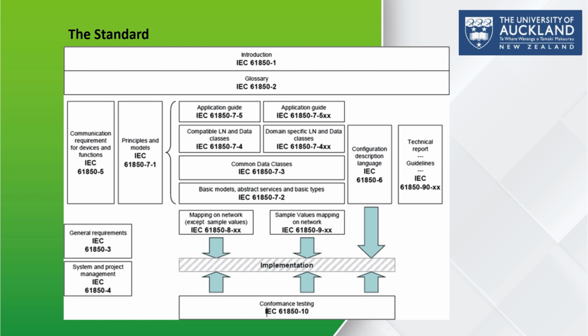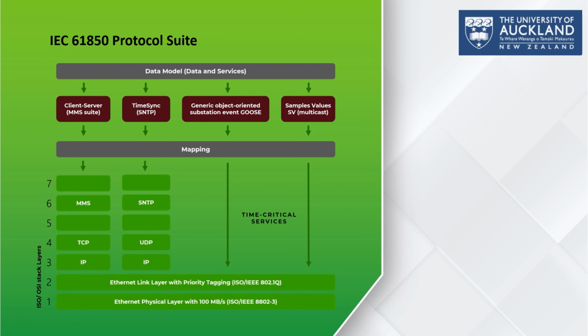So the next one is the IEC 61850 protocol suite. The diagram represents the communication architecture of the IEC 61850 standard, which is used in modern digital substations to ensure reliable, fast, and standardized data exchange. At the higher level, in the data model, I mean data and services, which defines what types of information are exchanged and how they are structured.